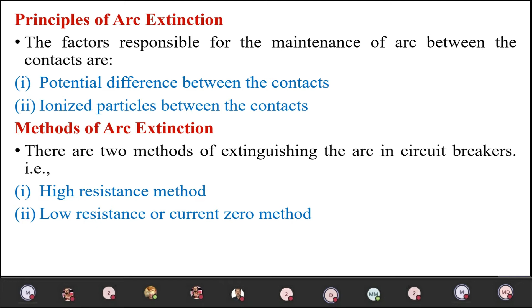So in the first method, that is the high resistance method, the arc resistance is made to increase with time, so that the current is reduced to a value which is insufficient to maintain the arc. Consequently, the current is interrupted or the arc is extinguished. So this is the first method, high resistance method. The principal disadvantage of this method is that enormous energy is dissipated in the arc.